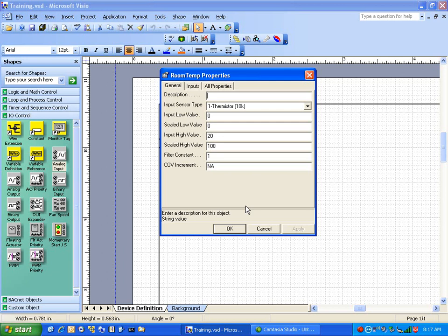So, for example, space temperature is not a value that changes very often by very large amounts. So what I like to put in for a COV for space temps is a 0.2. I like to put in a value of 0.2 for space temperature sensors. What this means is this space temp will not write back and forth to the UNC until it has actually gone beyond 0.2 degrees.